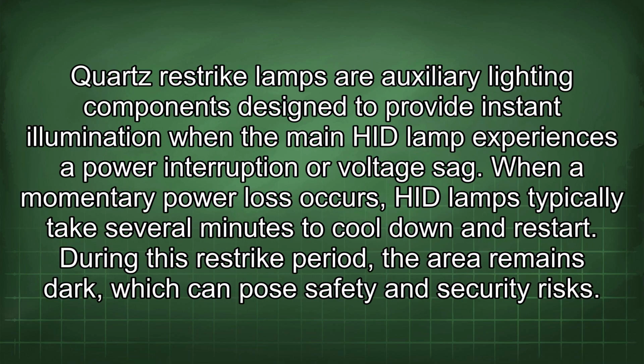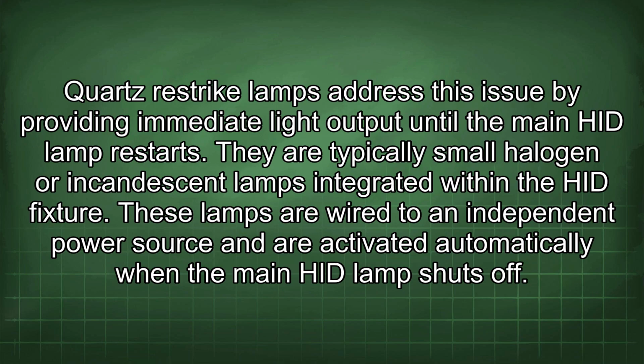Quartz restrike lamps are auxiliary lighting components designed to provide instant illumination when the main HID lamp experiences a power interruption or voltage sag. When a momentary power loss occurs, HID lamps typically take several minutes to cool down and restart. During this restrike period, the area remains dark, which can pose safety and security risks. Quartz restrike lamps address this issue by providing immediate light output until the main HID lamp restarts. They are typically small halogen or incandescent lamps integrated within the HID fixture. These lamps are wired to an independent power source and are activated automatically when the main HID lamp shuts off.